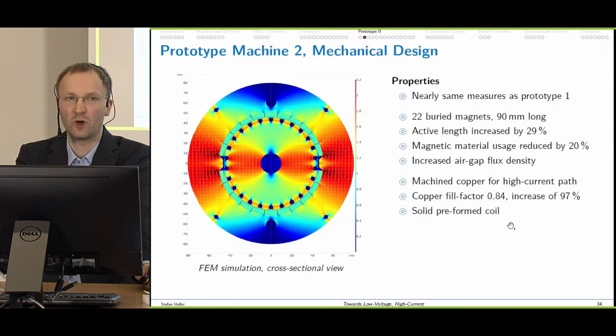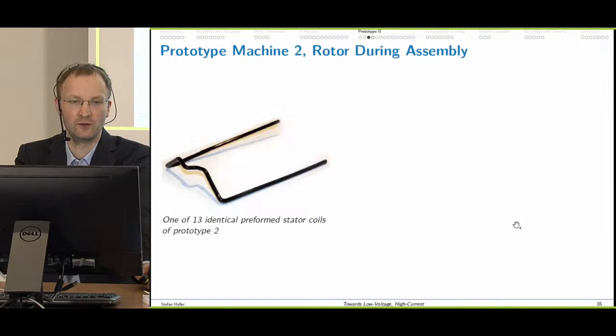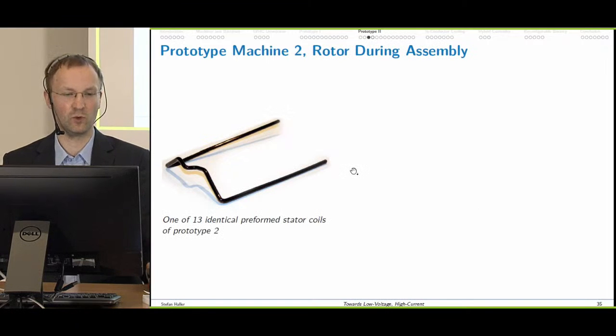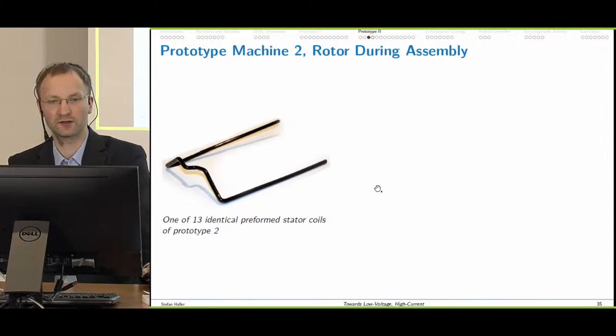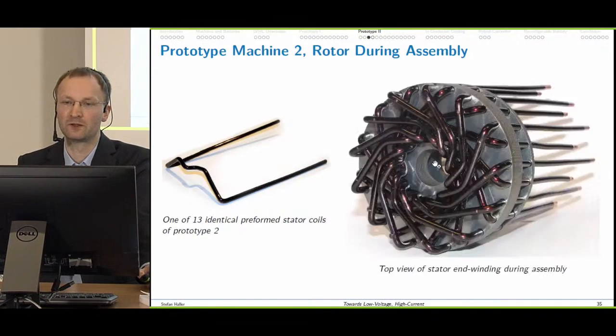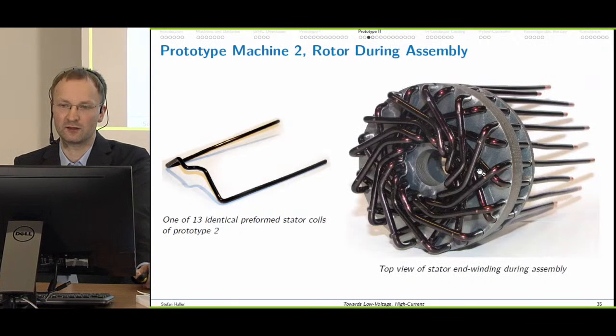We now use machined copper parts for all high current paths, and the copper fill factor has nearly doubled, reaching 0.84. That was achieved using solid preformed coils. Let's have a look at them. This is one of the 13 identical coils, here during the assembly process in the inner stator of the machine.